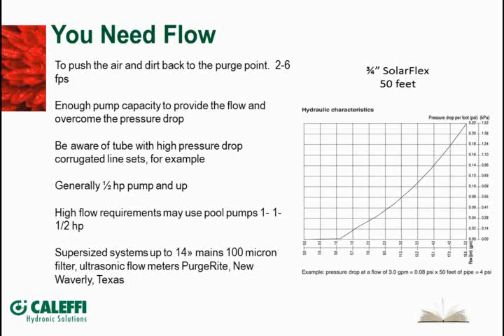Most of the time, a half-horsepower pump would work for my small residential jobs. I did have a larger swimming pool pump, a horse and a half, for bigger jobs, or for some of the smaller loop fields in the geo systems, you could get away with that. There's going to come a point, on the commercial jobs with big-size main piping, where you might want to hire somebody who has the equipment and the knowledge to purge the system out.